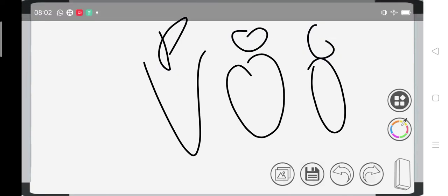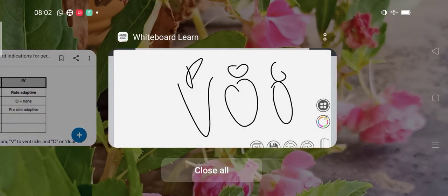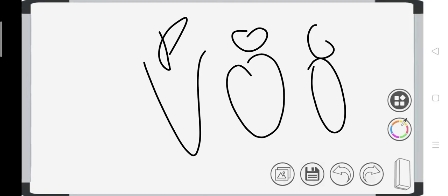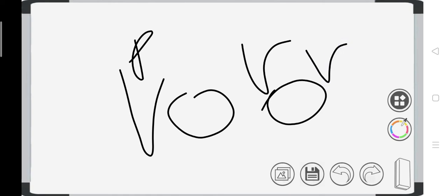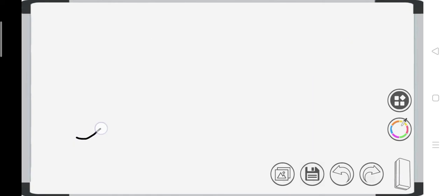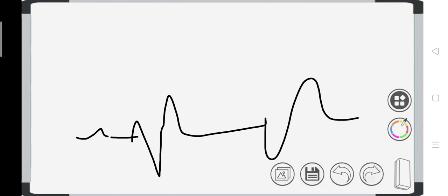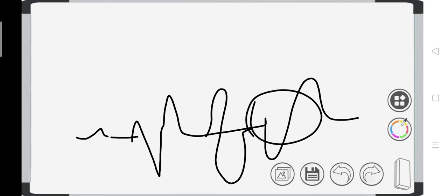Whatever the ventricle does, in VOO mode the ventricle will be paced, whatever the sinus rhythm ventricular activity is. So it is different from VVI in that there is a P wave, and then there is ventricular pacing at a fixed rate coming. Even if in between there is a ventricular depolarization of its own, there is no compensatory pause. It will not readjust for the normal sinus rhythm.